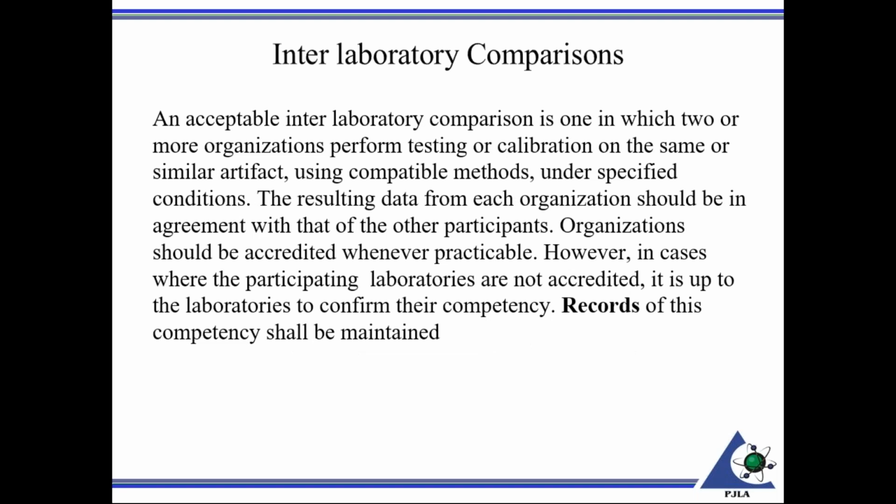All right, interlab comparison. These are perfectly acceptable. You don't have to get prior approval for doing an interlab comparison. An acceptable interlab comparison is one in which two or more organizations perform testing or calibration on the same or similar artifact using a compatible method under specified conditions. Data for each organization shall be in agreement with that of other participants.